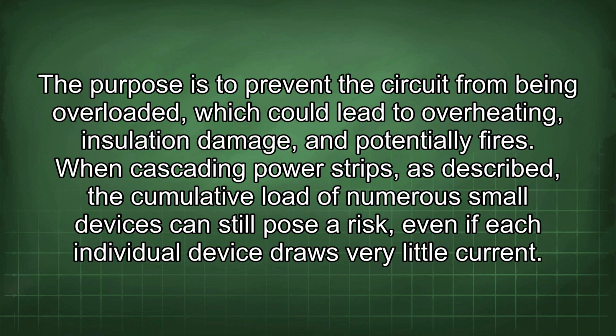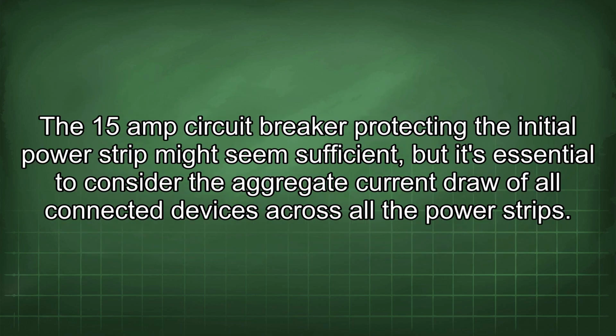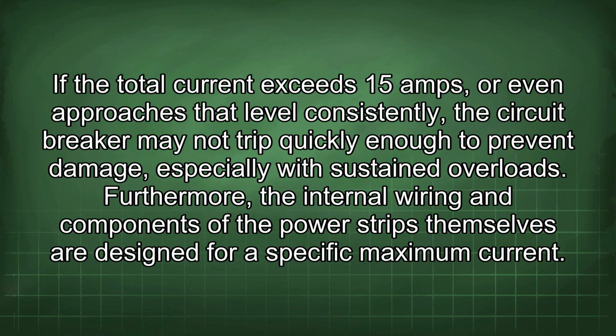When cascading power strips, as described, the cumulative load of numerous small devices can still pose a risk, even if each individual device draws very little current. A 15 amp circuit breaker protecting the initial power strip might seem sufficient, but it's essential to consider the aggregate current draw of all connected devices across all the power strips. If the total current exceeds 15 amps, or even approaches that level consistently, the circuit breaker may not trip quickly enough to prevent damage, especially with sustained overloads.